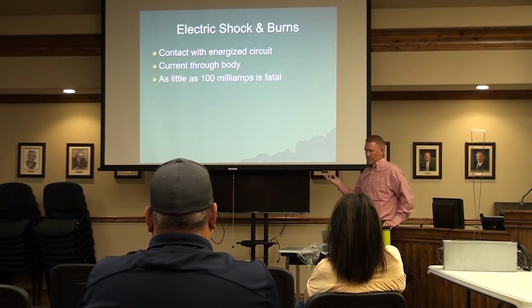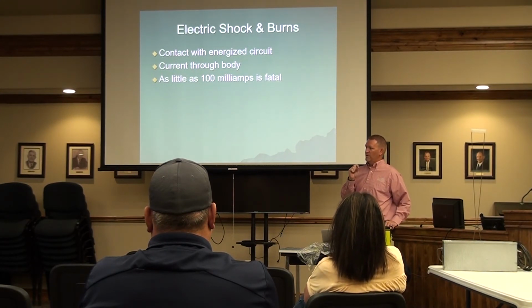GFCIs, like you have in your bathrooms and kitchens, have a 4 to 6 milliamp threshold, 5 plus or minus 1. That's the standard they're listed to. They want it set to a level where if it detects anything 4 to 6 milliamps, it trips and clears the shock hazard.